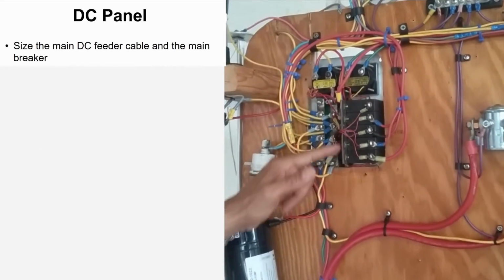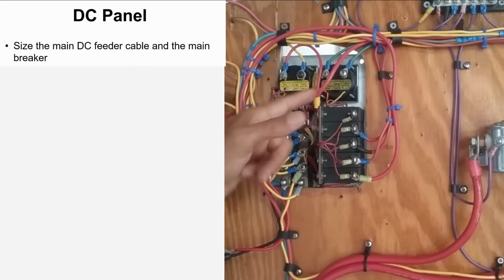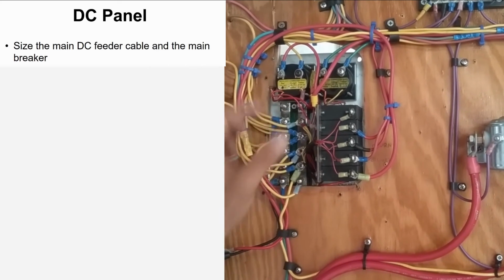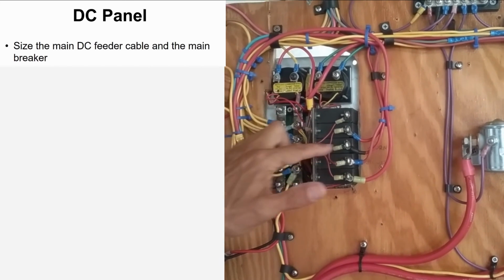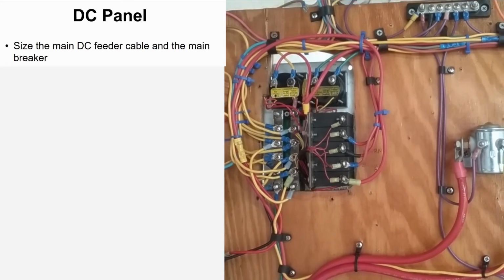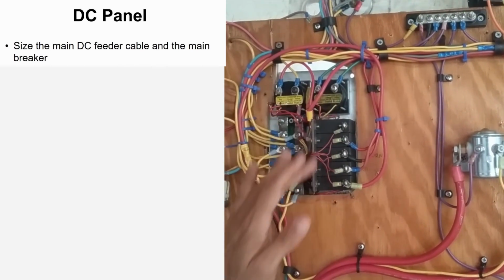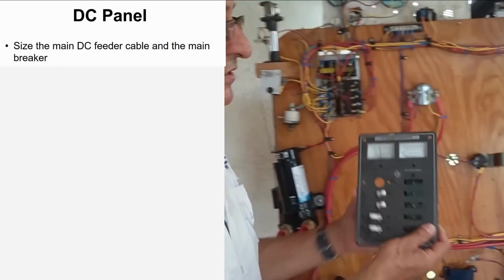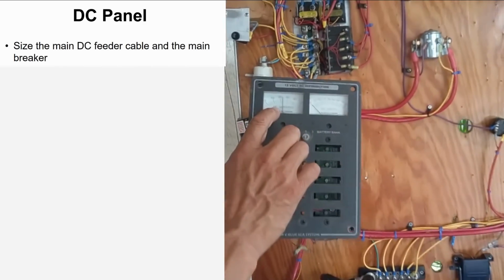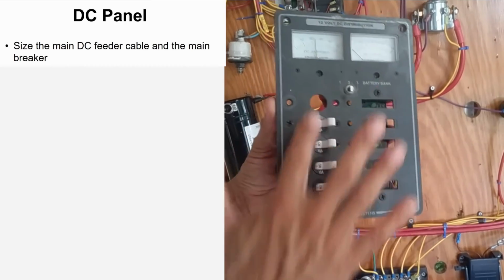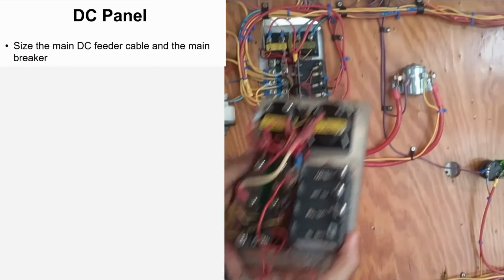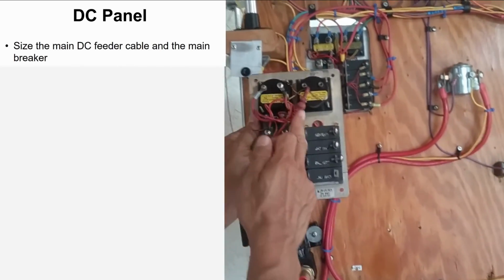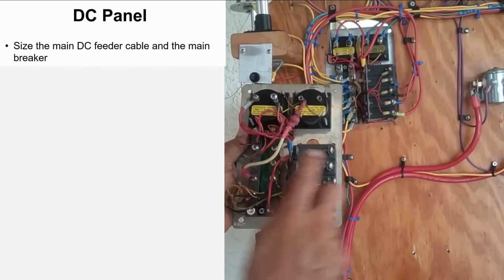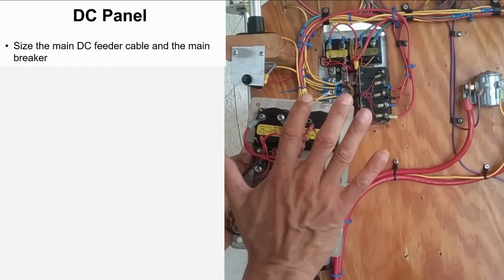This is the positive bus bar, this is the feeder for the positive bus bar, and those are the individual breakers. This is very important. In this particular case, the front of this panel has the ammeter, the voltmeter, and the individual breakers. In the back, it's exactly like this: the positive bus bar, the output of the breakers, and the voltmeter and ammeter.